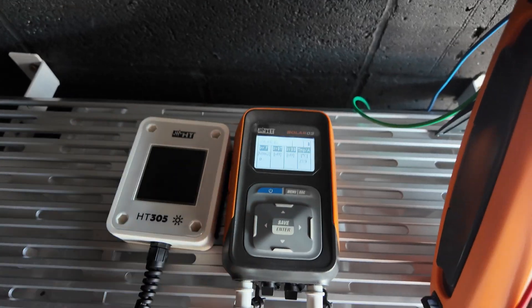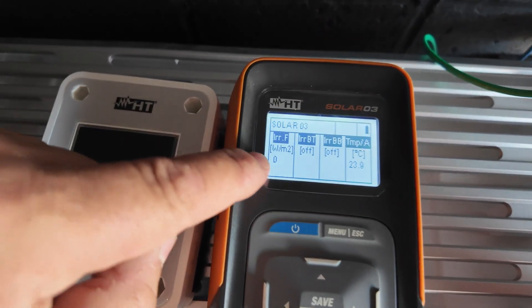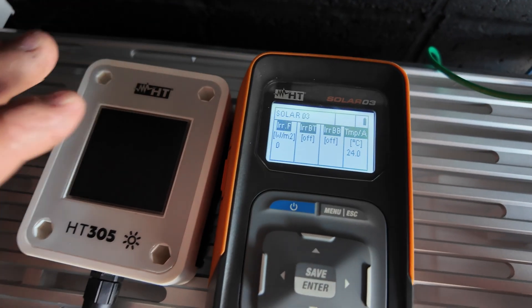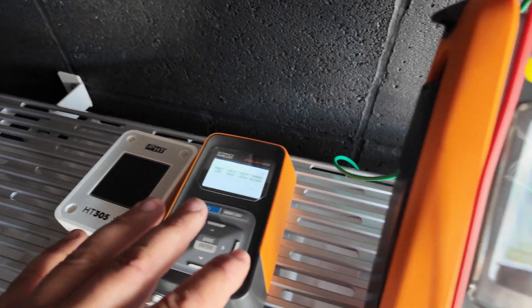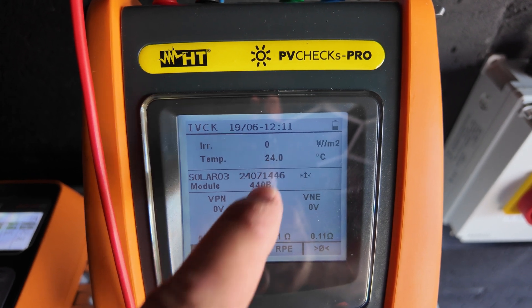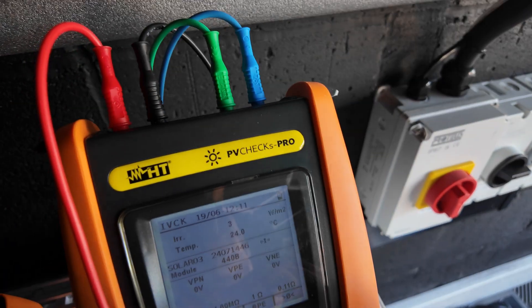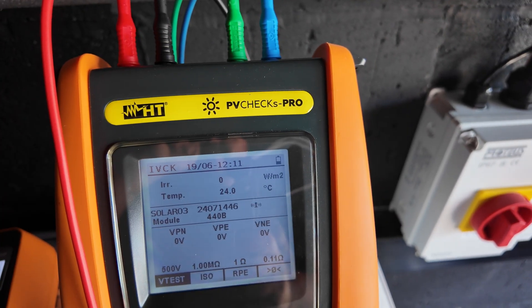Your next step is to get the SOLAR 03 set up. You can see there are four inputs on the bottom of here and it shows you as soon as you turn it on what's going where — so we've got our irradiance meter into the first terminal and our temperature sensor into this end one. It's automatically paired with the test set. You can see we've got an irradiance value of zero because we're inside, but it's jumped up to seven. Once we take it outside that'll fire right up, and we've got our temperature of 24 degrees which is correct.